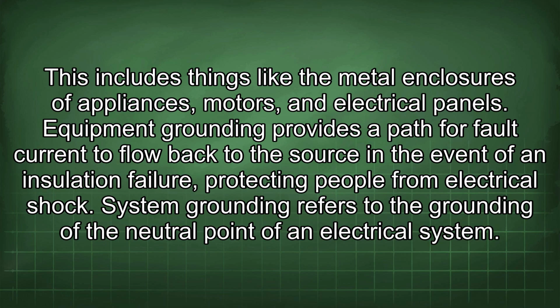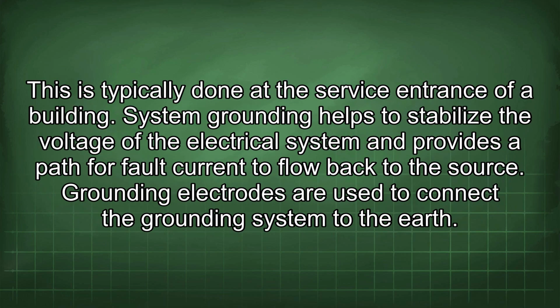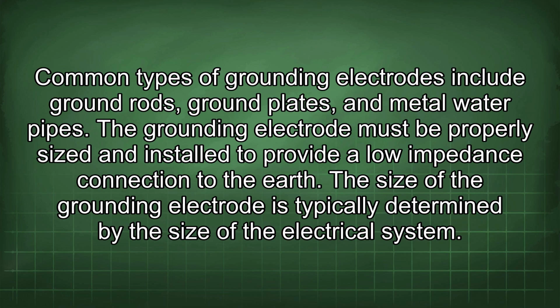System grounding refers to the grounding of the neutral point of an electrical system. This is typically done at the service entrance of a building. System grounding helps to stabilize the voltage of the electrical system and provides a path for fault current to flow back to the source. Grounding electrodes are used to connect the grounding system to the earth. Common types of grounding electrodes include ground rods, ground plates, and metal water pipes. The grounding electrode must be properly sized and installed to provide a low impedance connection to the earth. The size of the grounding electrode is typically determined by the size of the electrical system.